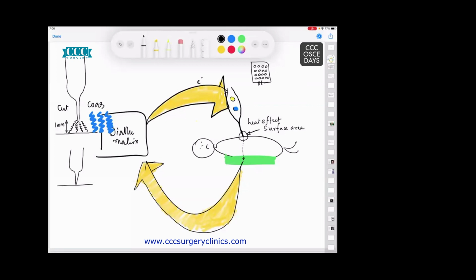The minute you touch the thing on the tissue, the tissue undergoes only one effect, something called desiccation. It dries up. And the cutting and the coagulation effect that you wanted doesn't occur in the way you want it to. So the only lesson from today's class is, the next time, or today evening, if you are planning to do an operation, just hold the active electrode a millimeter away from the tissue.